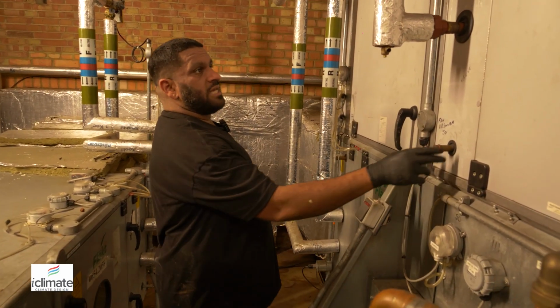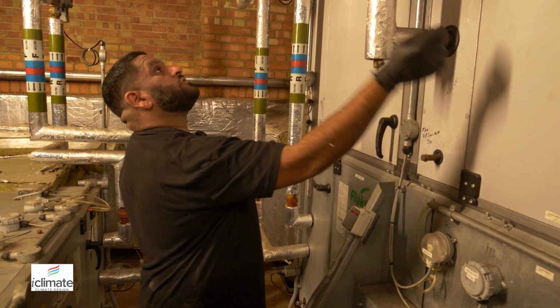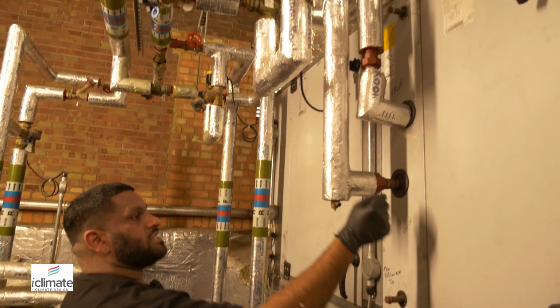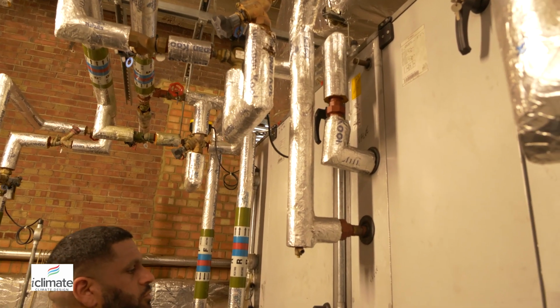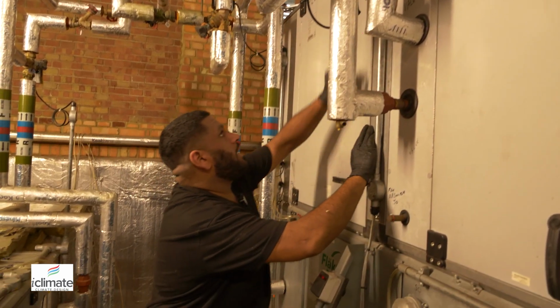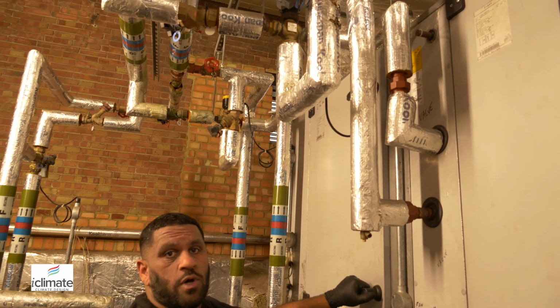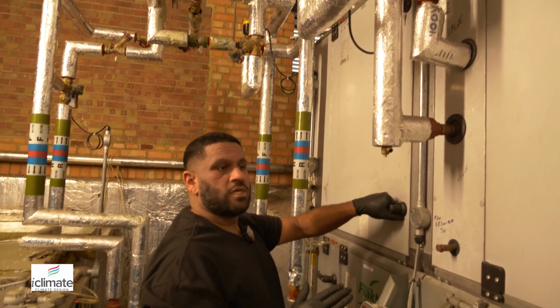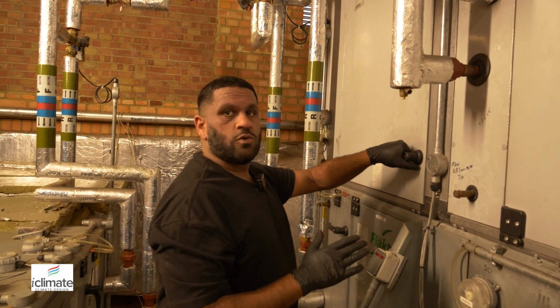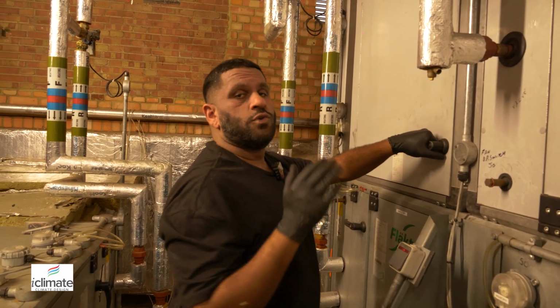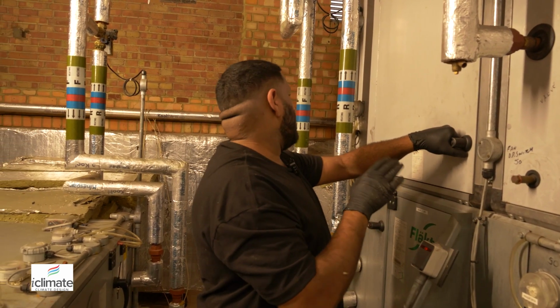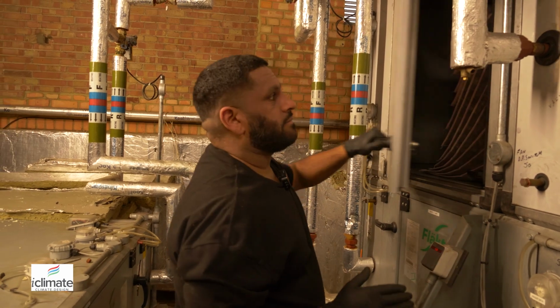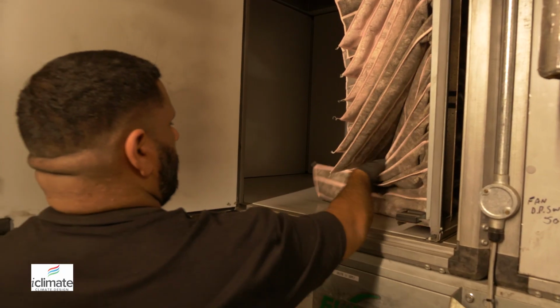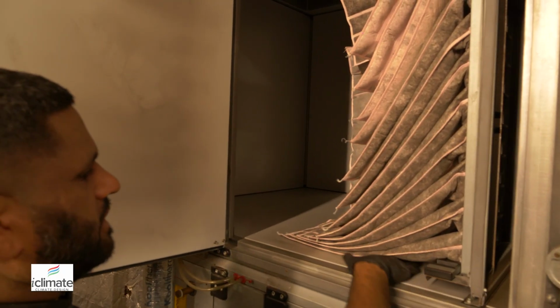With there being coils in here, there's another coil in here, and that's for the cooling circuit, right? You can see it's got a fan switch and a drain. And then when you open up the compartments, we don't advise, if you're not trained or skilled in dealing with plant rooms or working in a plant room environment, you do not open the air chamber until the air handler is isolated, right? So in here, this is a very clean compartment. You can see how we've kept it nice and clean.